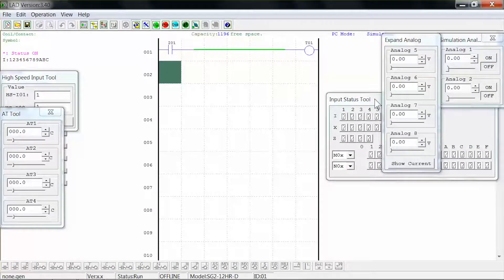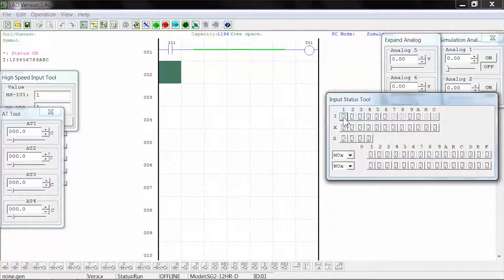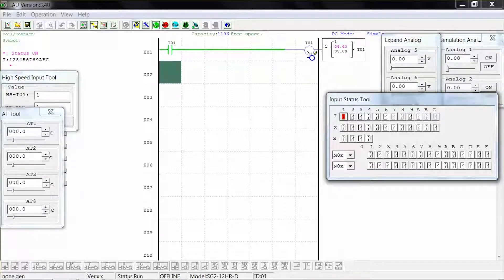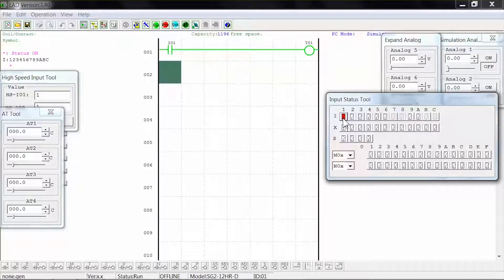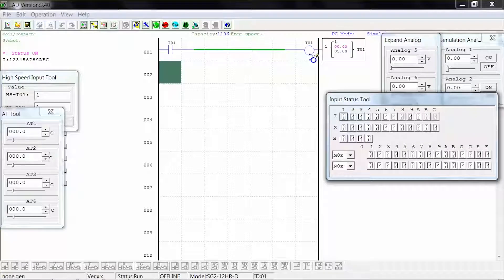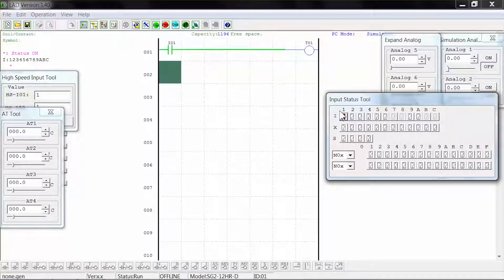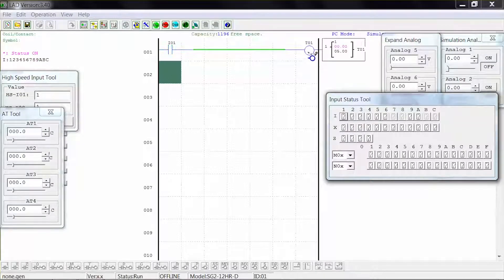On our input status tool we can select input 1 and the timer will start to count to 5 seconds. When 5 seconds is reached the coil will activate and stay activated until you release input 1, at which point the coil deactivates and the timer is reset. If you release input 1 before the coil activates, the timer will reset and the coil will remain unactivated.